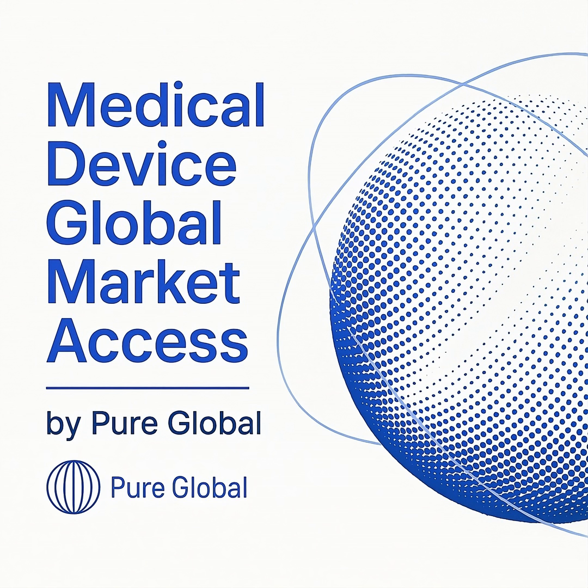In summary, while your FDA PMA provides a strong foundation of evidence, you must still undergo a full Canadian regulatory process. This involves obtaining MDSAP certification, securing an MDEL for the relevant parties, and submitting a complete medical device license application that is tailored to Health Canada's specific formatting, labeling, and evidentiary requirements.